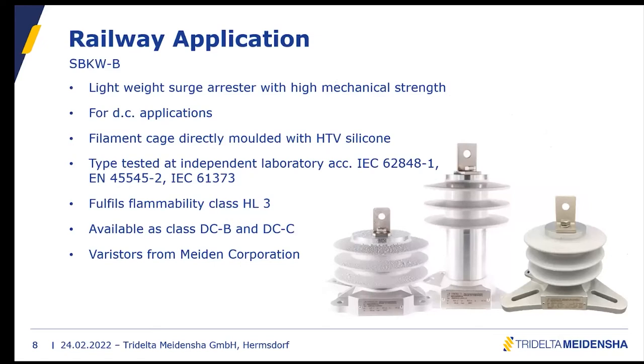Let's take a closer look at the SBKW-B. This is for DC applications — a relatively lightweight surge arrestor with high mechanical strength. The technology behind it is a filament cage directly molded with HTV silicone from Wacker. It is type tested at independent laboratories according to the relevant standards, and it fulfills flammability class HL3, which is the highest possible class, so it can be used for every application.